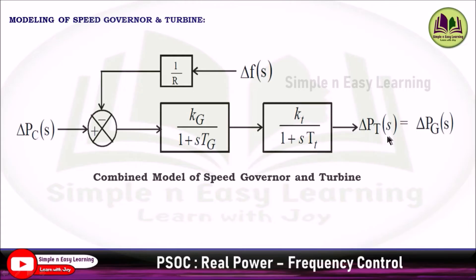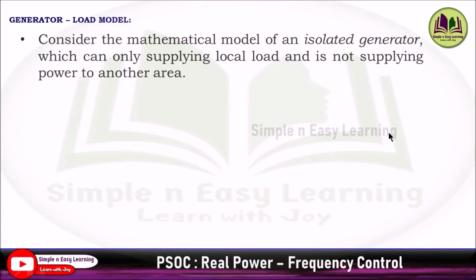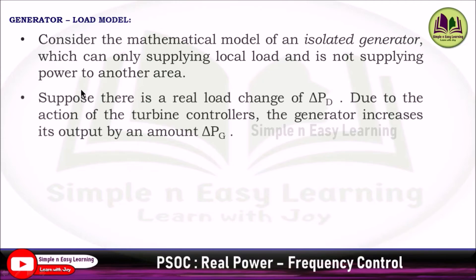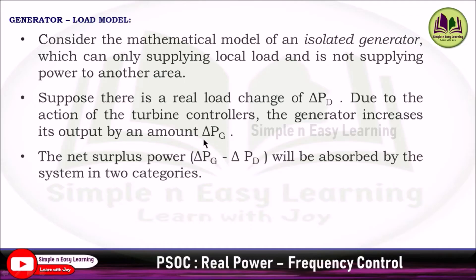The combined setup of speed governor and turbine adds the turbine block Kt/(1+s·Tt) after the governor, giving output del_Pt(s). Now for the generator-load model: consider the mathematical model of an isolated generator supplying only local load. If there is a real load change del_Pd, the generator increases its output by del_Pg. The net surplus power del_Pg − del_Pd is absorbed by the system in two categories.